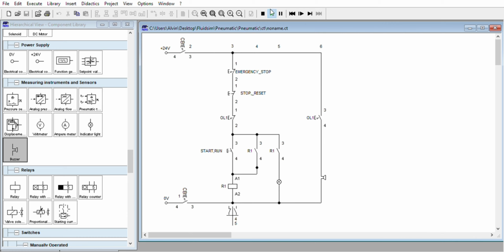So remember, the thermal overload relay has a mechanism that will be triggered by the overheating of the thermal element, the bimetal strip. Okay, once the motor is in operation, we will simulate the motor later. So this is turning on the motor via another contact, let's say a power contact. So we will simulate this one manually. So the supply here will be cut off. The supply will be here to signal the alarm.